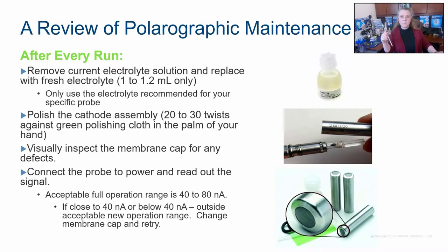If you've just rebuilt the probe and you're getting a 40 nanoamp signal, remember we talked about how the electrolyte will change over the course of a run, and it will read artificially low. If the best you're ever reading is 40 and then you read lower than that, that's outside of the usable range of this probe. So you want to start as close to 80 as you can at the beginning of a run, because it will drop. If it's below 40 nanoamps, this sensor is not going to survive a full run. If it's 50, I'd be very cautious. If it's 60, depending on the run, I might not be worried. 60 and above is really where you want to be for the Hamilton probes.